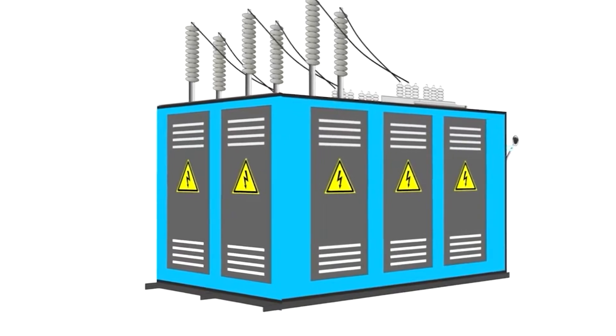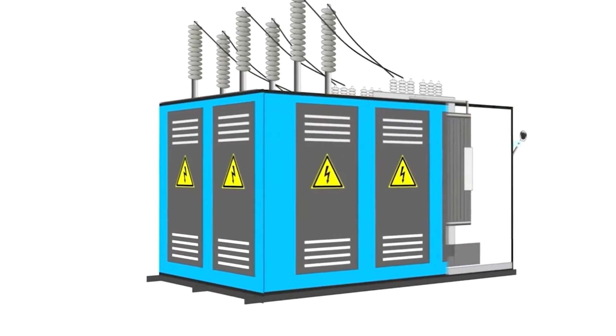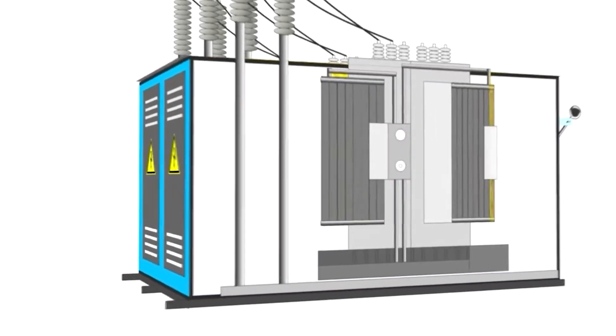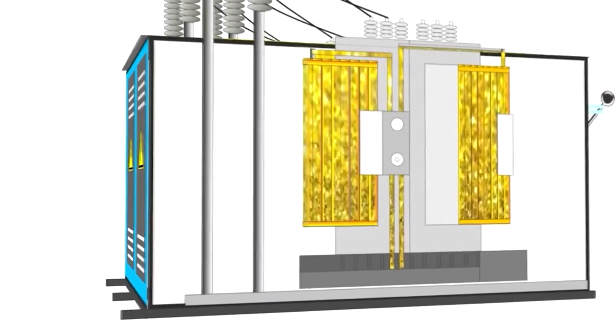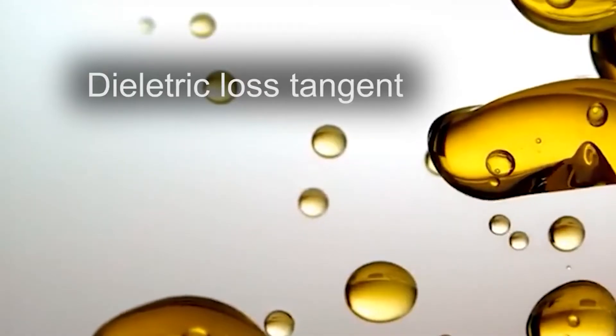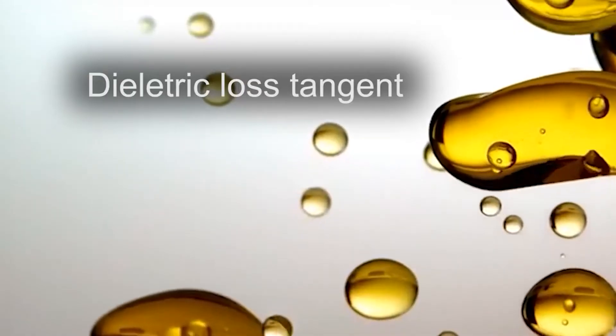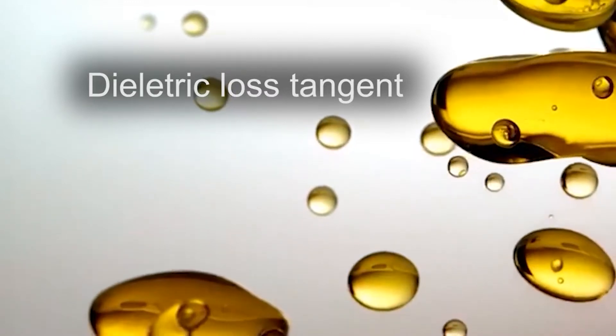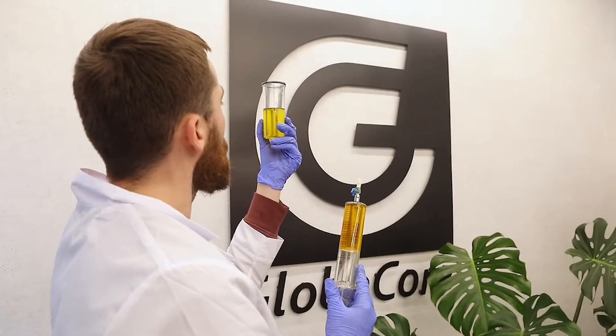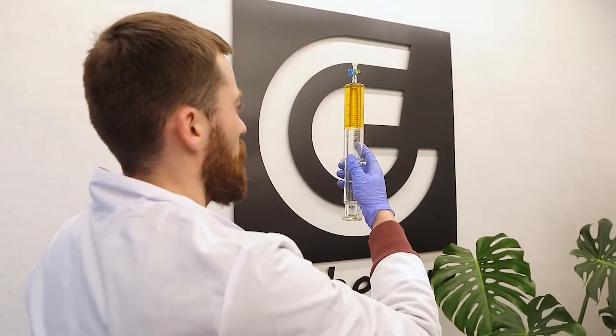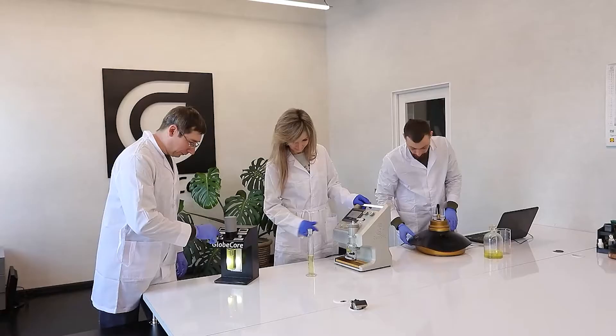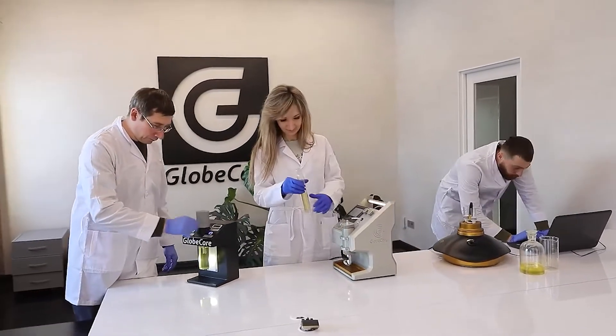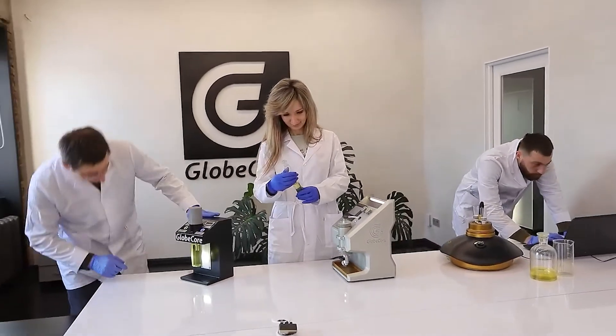To obtain complete information about the dielectric properties of transformer oil, the dielectric loss tangent is measured. In the case of new oils, this parameter makes it possible to assess the quality and degree of their purification, and in the case of used oils, the degree of their contamination and aging is estimated.